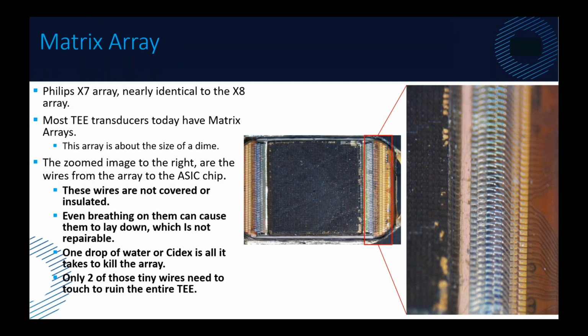One of the things that we talk about in ultrasound a little bit is that in an endoscope, everything around the transducer is built to support that little camera. In ultrasound, everything is built to support the ultrasound array. So this is the actual array from a Philips X7-2T TEE probe, which is nearly identical to the X8. Now they've come out with the X11-4, which I haven't seen the inside of. I highly doubt they've changed their manufacturing concept. It's just a different crystal with a higher frequency.